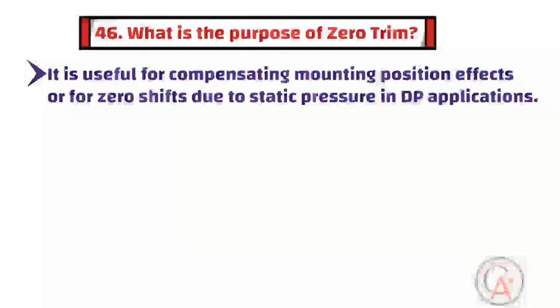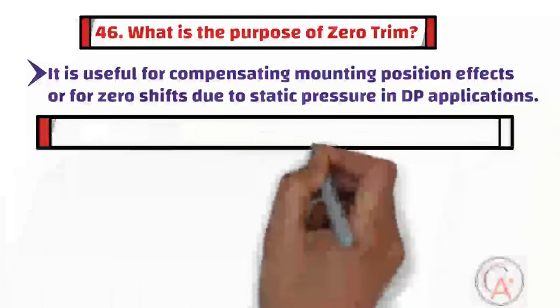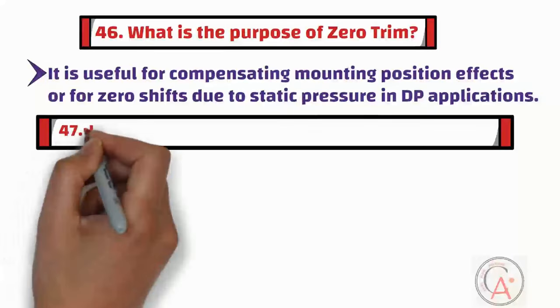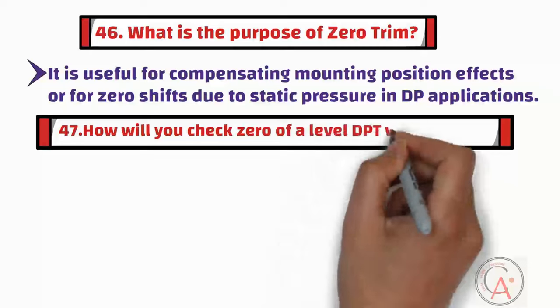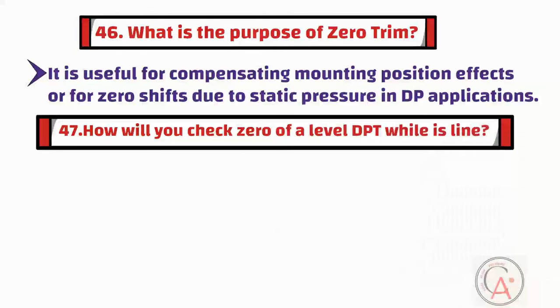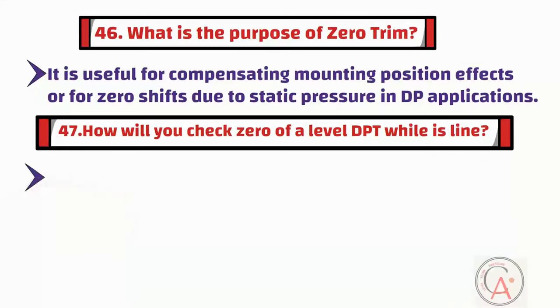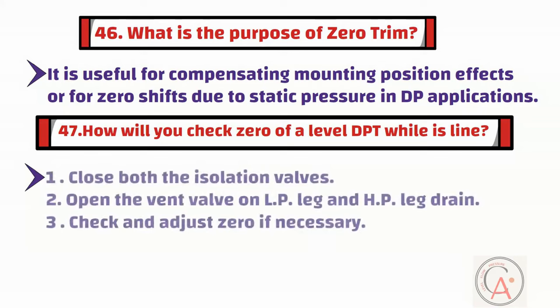The forty-seventh question is: how will you check the zero of a level DP transmitter while it is in line? To check the zero of the DP transmitter, first close both the isolation valves. Then open the vent valve on the LP leg and HP leg drain. Finally, check and adjust the zero if necessary.